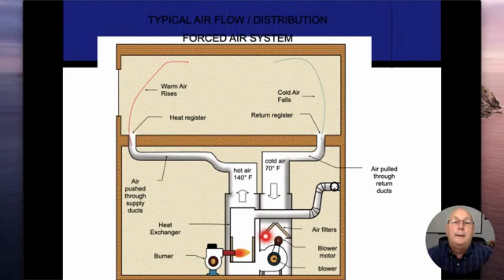All right. And then if we think about it, even if I had a hole in my heat exchanger, because now if this is under zero pressure, because I do not have an inducer fan. If I had an inducer fan, I would create a negative pressure inside here. And then I would also have a positive pressure being created on the outside of the heat exchanger. If I did have a hole or crack or opening in there, that means that the air would be flowing into the heat exchanger instead of allowing gases to escape.